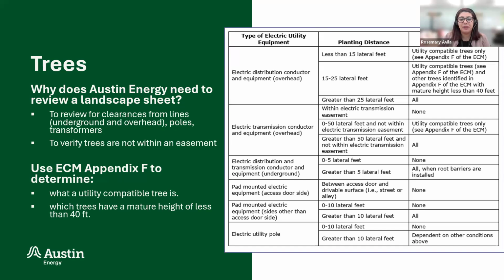If you look down where it says poles, no tree can be within 10 feet. If you're greater than 10 feet, there are other conditions we might ask about, like tree trimming. But it's an easy chart to follow - you use this with your ECM, and that's what we're looking for.